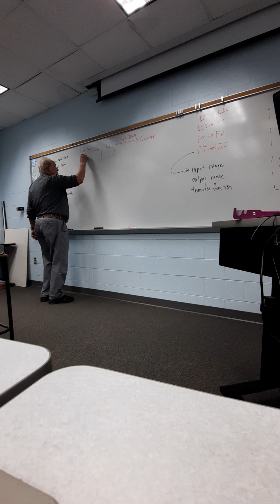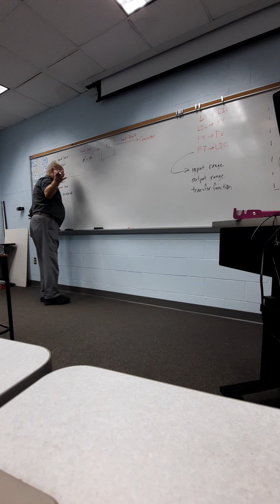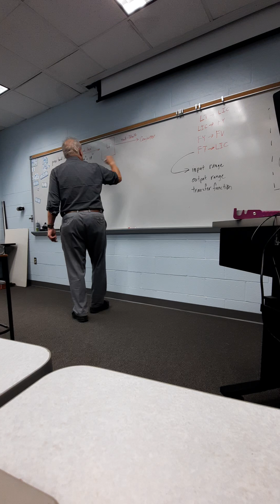So our tank level is 0 inches to 10 inches. Now we set an input range, which effectively is our proportional band, because that's what we want to transmit. Our actual proportional band may not be that, because we may hit limits on the output due to our transfer function. We'll show that a little later on. We do have a fixed limit on this, and I'm going to use that fixed limit. Our output to the computer is going to be 4 milliamps to 20 milliamps.